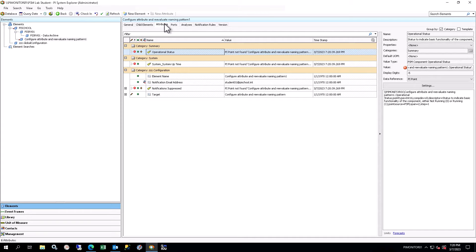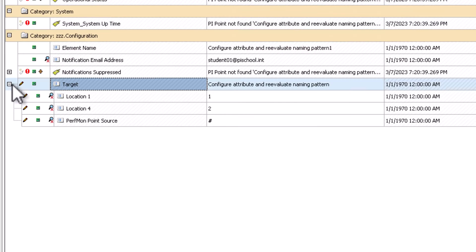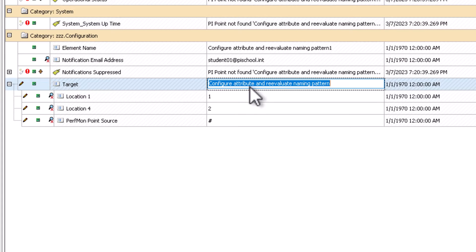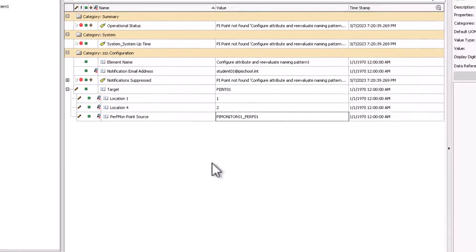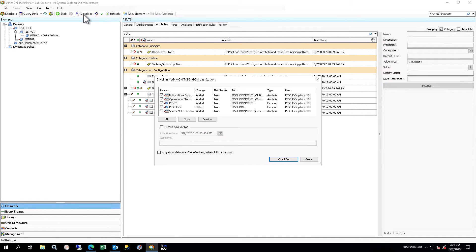You will need to fill in certain details that were provided at the beginning of this document in the target attribute. Target will be the machine name for the server, PI INT 01. The default values for location 1 and location 4 can stay the same. The PI Perfmon point source will be set to the point source for the Perfmon instance that is retrieving the performance counters for this server — in this case, PI Monitor 01 underscore PERF 01. Ensure that the values you have entered look exactly as shown. Check in your changes and refresh the view. At this point, your hierarchy should appear as shown.